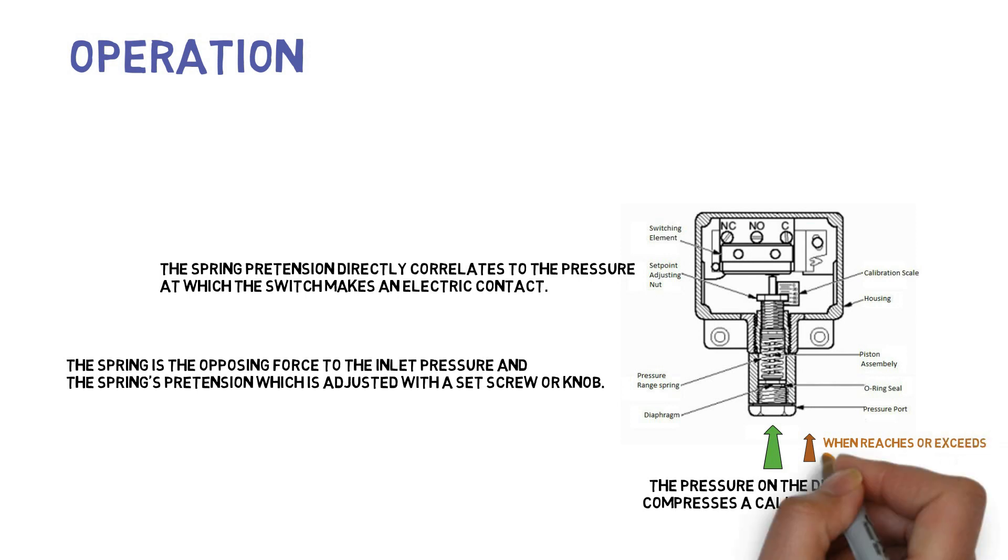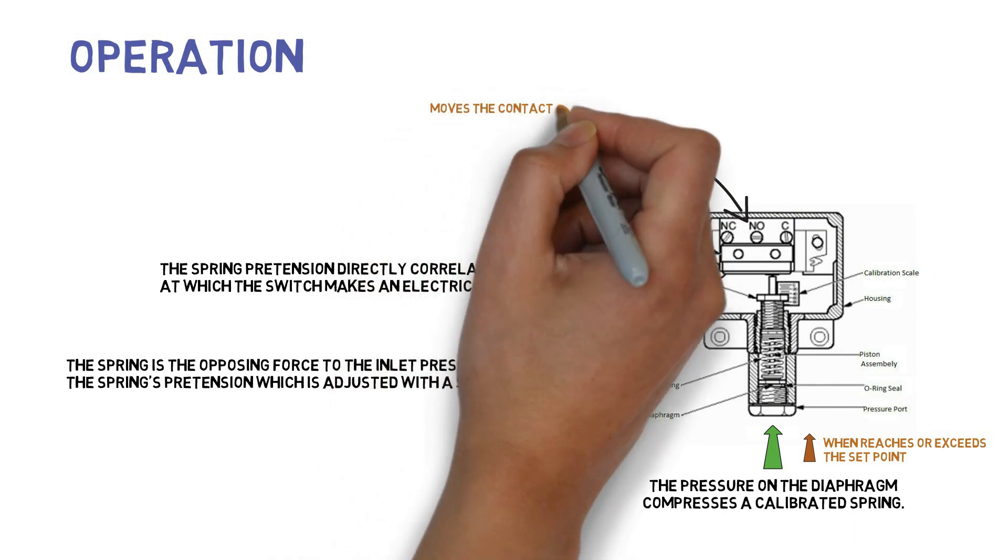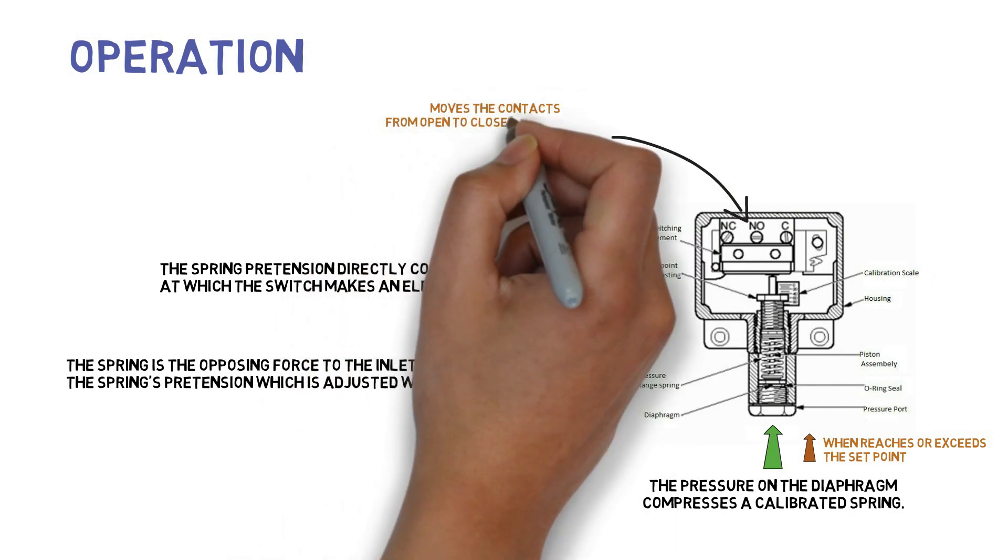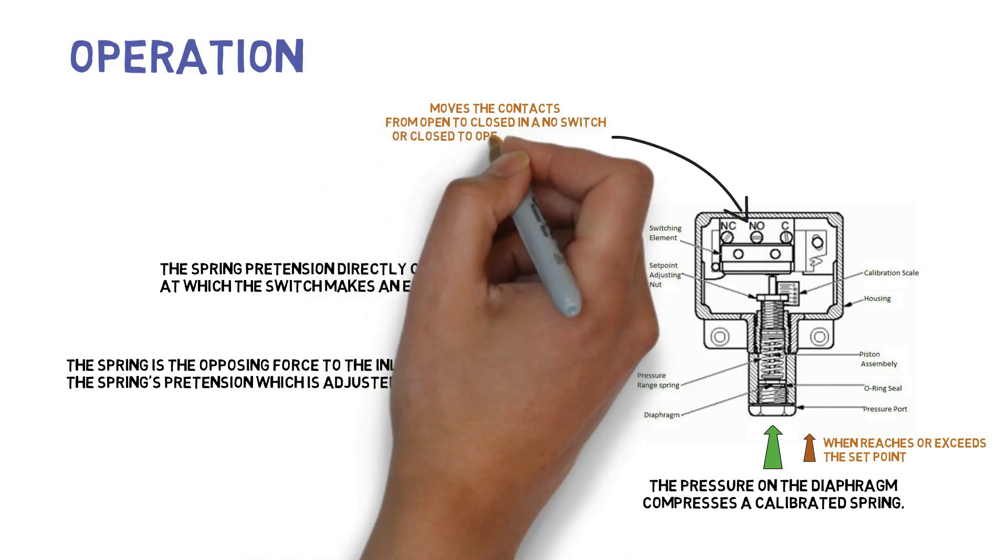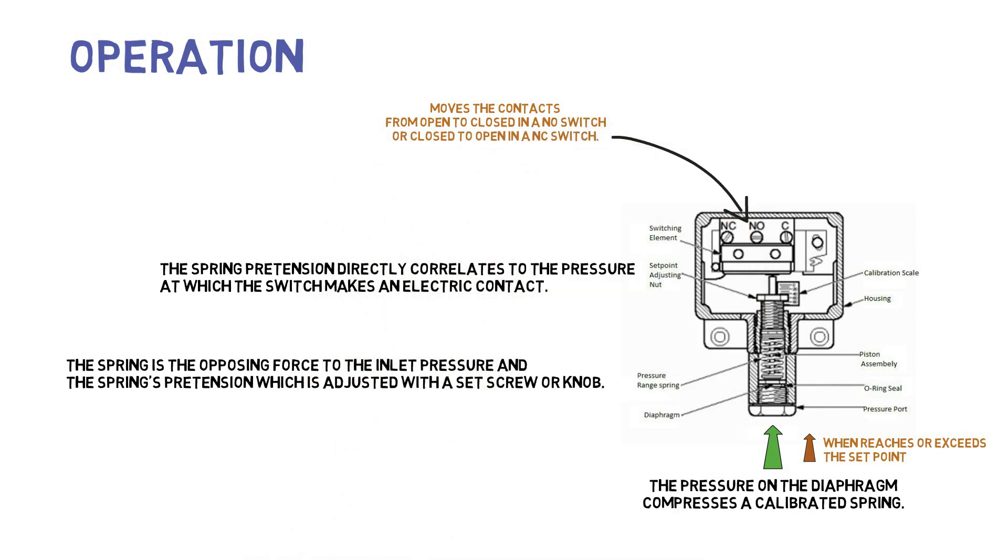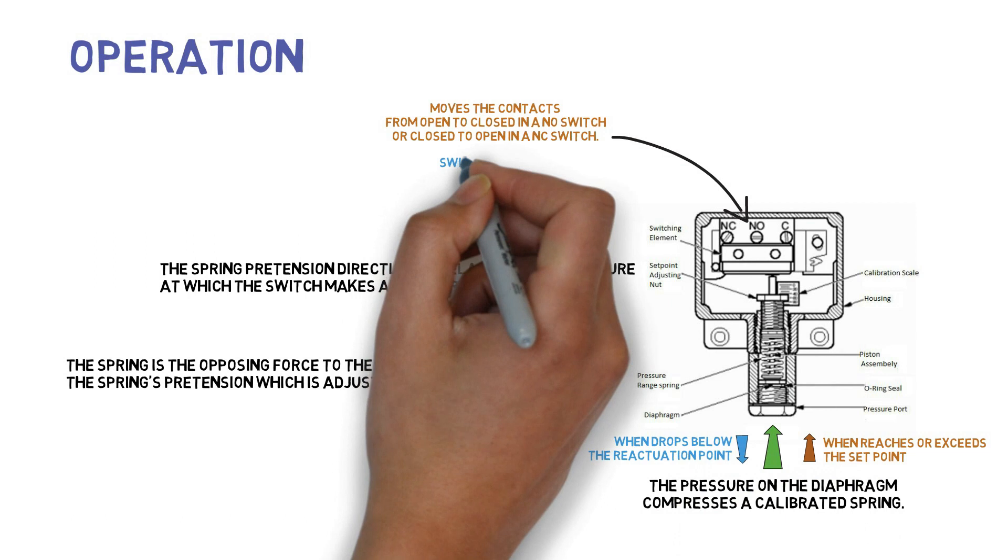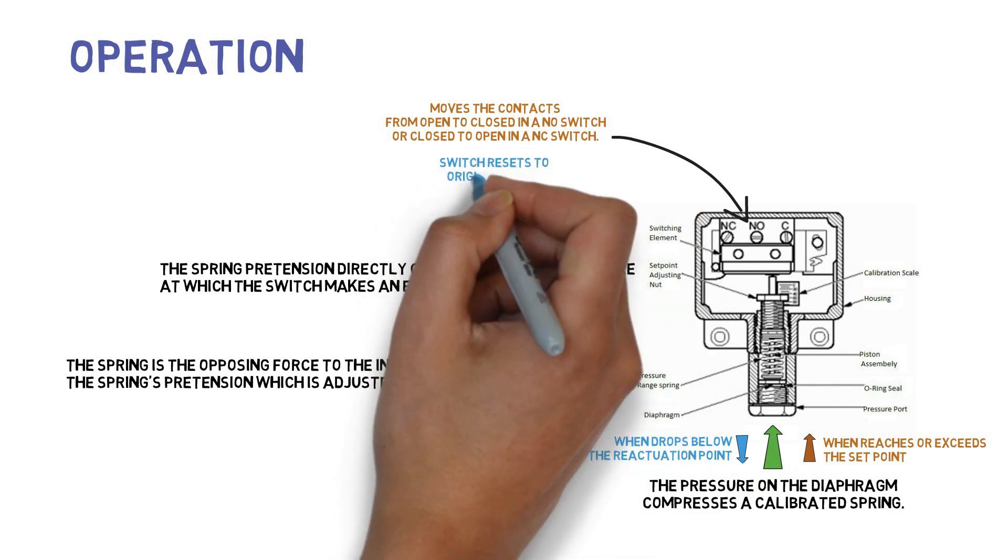When the pressure spring tension reaches or exceeds the set point, the switch moves the contacts from open to closed position in a normally open switch, or closed to open position in a normally closed switch. When the pressure drops, the switch resets to its original state.